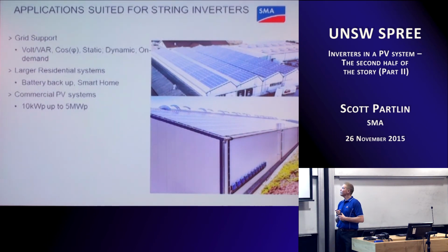When you start looking at commercial systems, here's an example of some commercial systems that I found on our image database at SMA. String inverters will tend to be a simpler option for realising that, and also a lower cost option because they're normally a lot simpler. They're very large arrays with fixed string runs. It's quite easy to get them all installed and hooked up, and the cost of components means that the lowest dollar per kilowatt hour ends up being delivered by a string inverter. And they have a natural limit. The string inverter in this sort of application, if it's low voltage connected, will have a natural limit probably up to about 0.5 megawatt, and if it's connected via an isolation transformer, either at a higher voltage, say 11 kV or higher, a natural limit up to about 5 megawatts. Beyond that, it starts to become less attractive to use something like a string inverter.